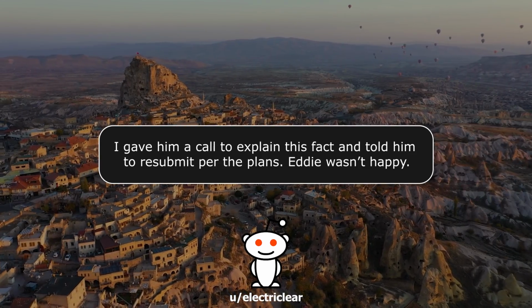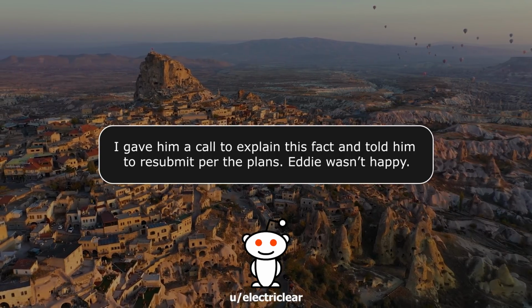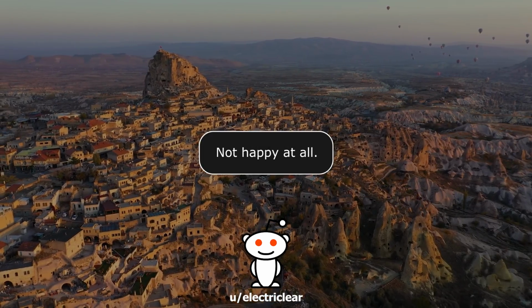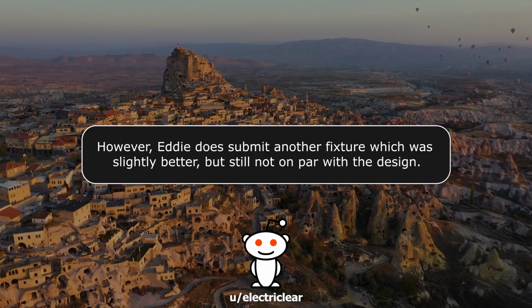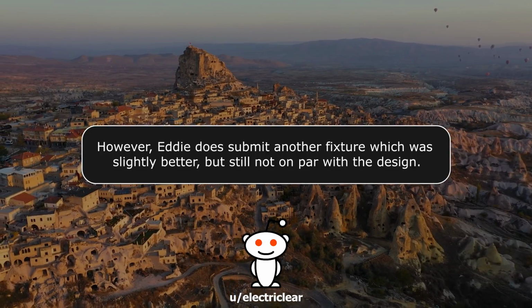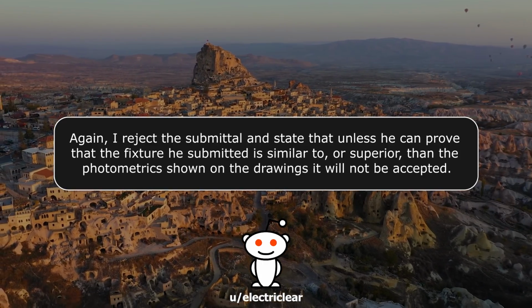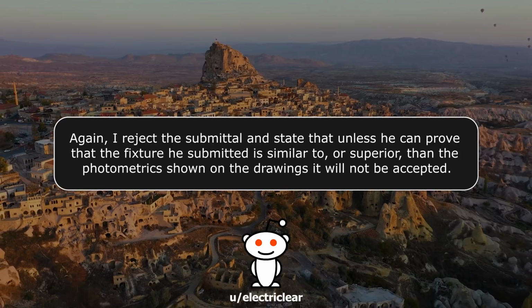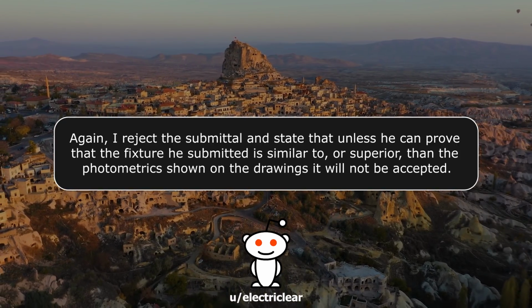I gave him a call to explain this fact and told him to resubmit per the plans. Eddie wasn't happy. Not happy at all. However, Eddie does submit another fixture which was slightly better, but still not on par with the design. Again, I reject the submittal and state that unless he can prove that the fixture he submitted is similar to or superior than the photometrics shown on the drawings, it will not be accepted.